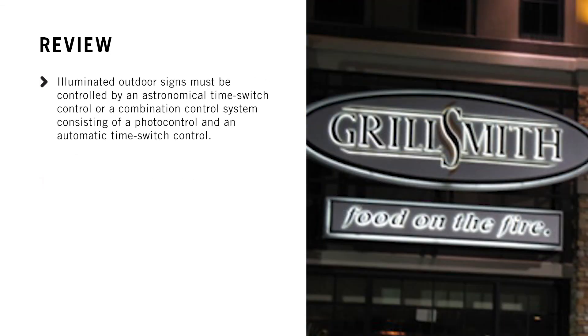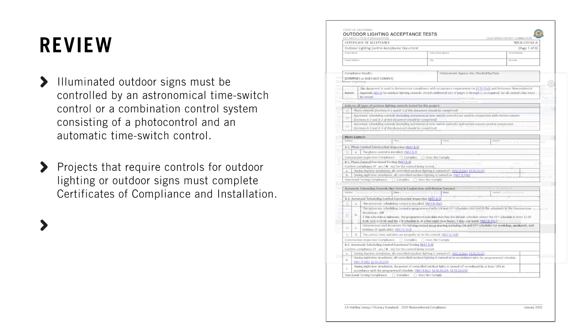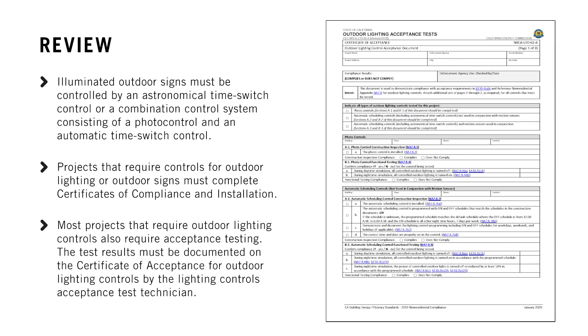Illuminated outdoor signs must be controlled by an astronomical time switch control, or a combination control system consisting of a photo control and an automatic time switch control. To demonstrate compliance with the Energy Code, projects that require controls for outdoor lighting or outdoor signs must complete certificates of compliance and installation. Most projects that require outdoor lighting controls also require acceptance testing, and the test results must be documented on the certificate of acceptance for outdoor lighting controls by the acceptance test technician.